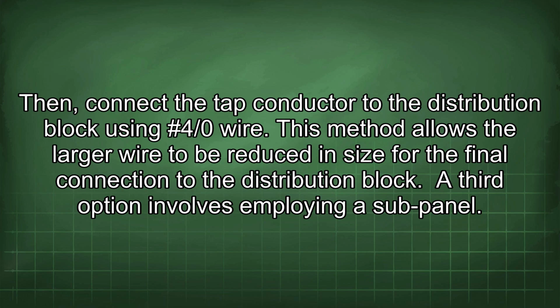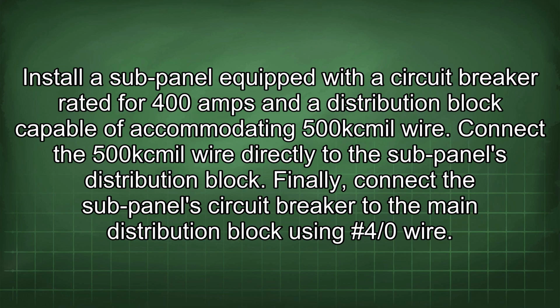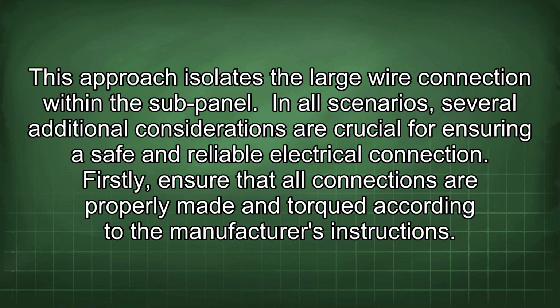A third option involves employing a sub-panel. Install a sub-panel equipped with a circuit breaker rated for 400 amps and a distribution block capable of accommodating 500 kcmil wire. Connect the 500 kcmil wire directly to the sub-panel's distribution block. Finally, connect the sub-panel circuit breaker to the main distribution block using #4/0 wire. This approach isolates the large wire connection within the sub-panel.